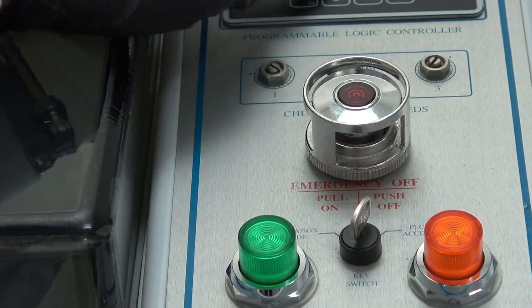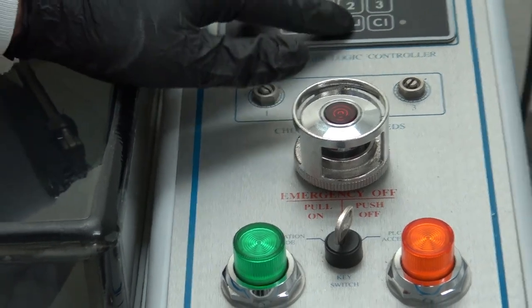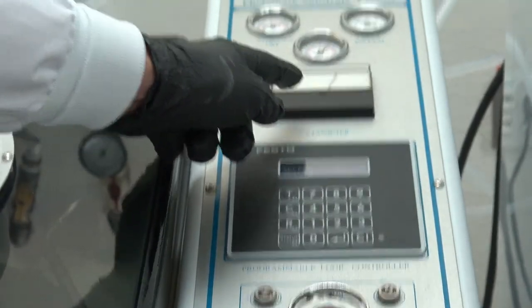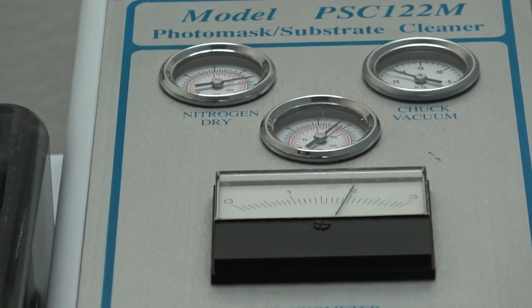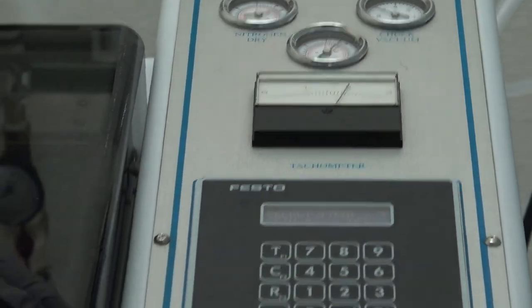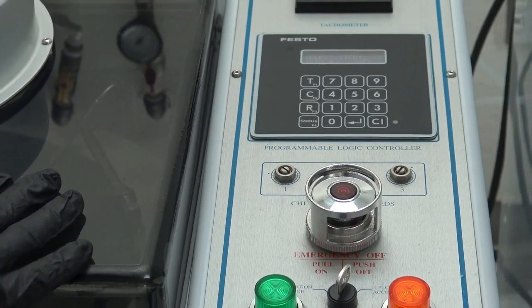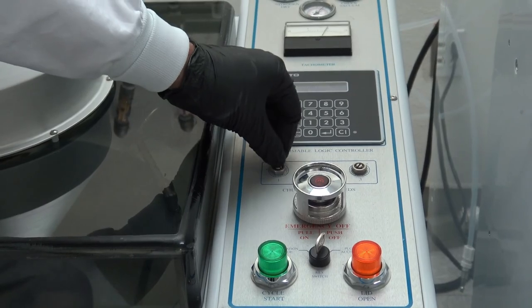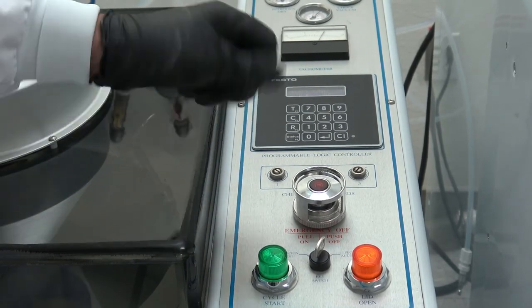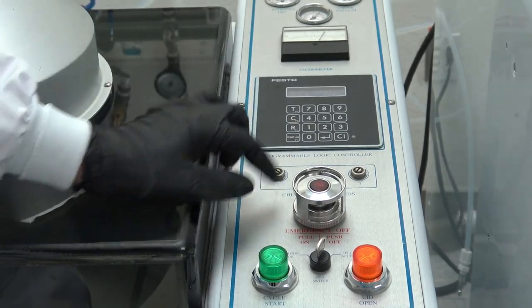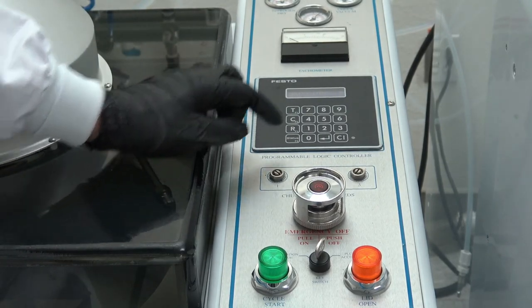So to then move on to 22. Press enter. And now this speed is similar. Move to 23. Now this speed is the high RPM spin speed. As you can see, it's up to 2000 RPM right there. I actually may have spoke a little bit out of turn on which ones, which of these initiate during which time. That can be confirmed in the manual for certain. And not only that, but during operation, you can manually adjust these to adjust the spin speeds to exactly how you'd like the system to perform during your process development time period. Do be careful when adjusting these spin speeds. A slight adjustment can make a big change in RPM. And you don't want to cause any damage to the system when doing large adjustments. So now I'll go ahead and turn it off. 20 is turn off. So now we have completed the basic training of the system.